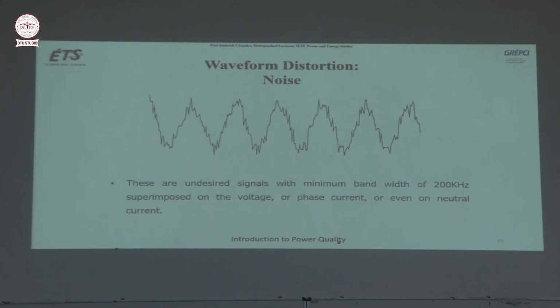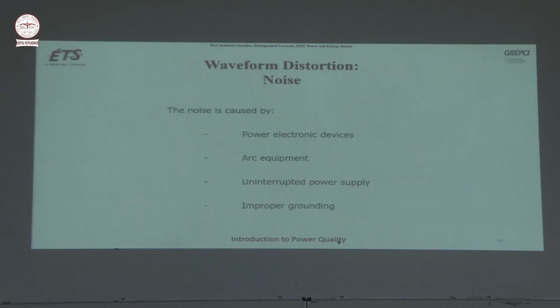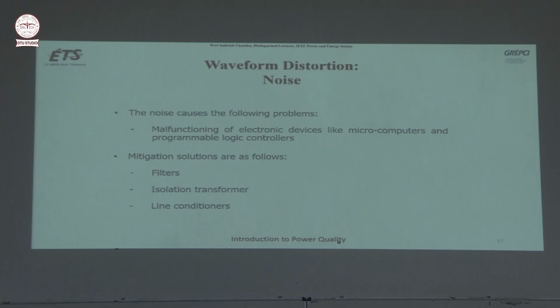Noise. These are undesirable signals. We're talking about waveform distortion, because we saw that these are undesirable signals with a minimum of 200 kilohertz superimposed on voltage, even on the neutral current. This is caused by power electronic devices, arc equipment, and improper grounding. The following problem: malfunction of electronic devices and programmable logic controller. Mitigation solution: filter, isolation transformer, line conditioner.